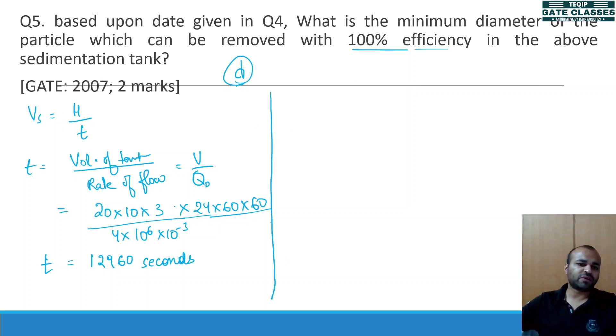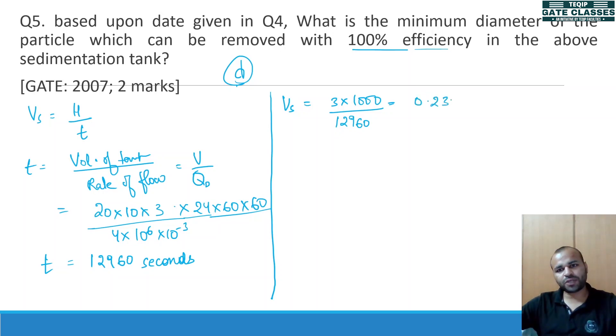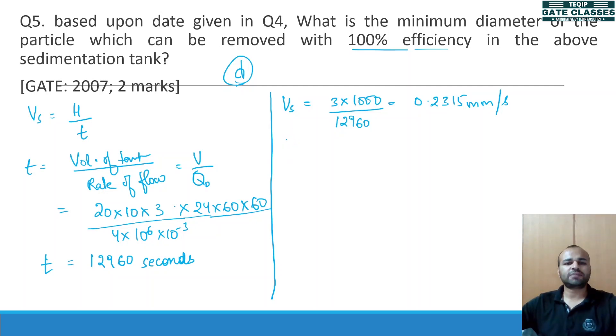Now we have calculated the detention time and we know the depth, so we can calculate the settling velocity. Settling velocity = depth / detention time, which comes out to be 0.2315 mm/s.